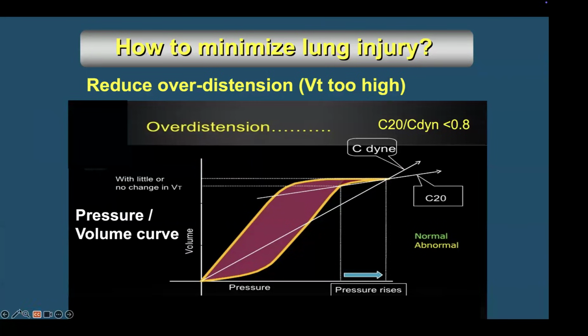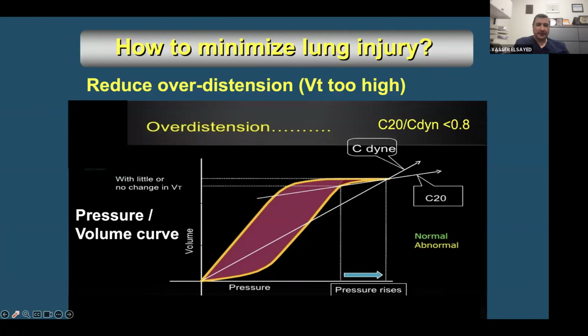Yeah, clear. So we have on the y-axis the volume and on the x-axis the pressure, and you have what's called the pressure volume curve. For this pressure volume curve, the perfect one is more upright. When you have it more horizontal, it means you have poor compliance. Number two, the bottom part here, when you have it very flat and lying, it also means poor compliance. It means that you have a long time between your preset PEEP and when the infant starts to breathe, so you need to move your PEEP higher.